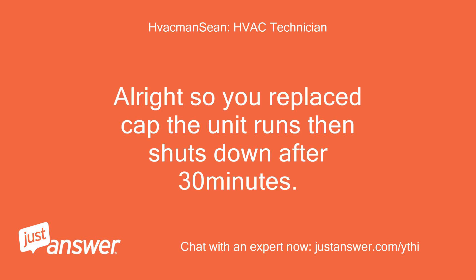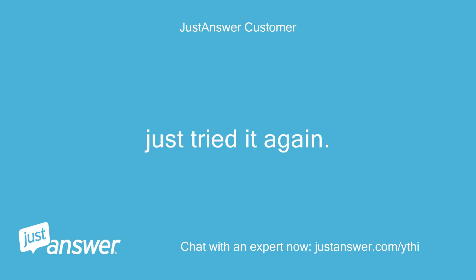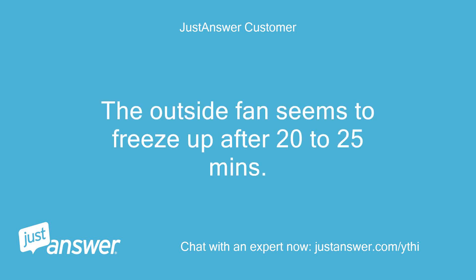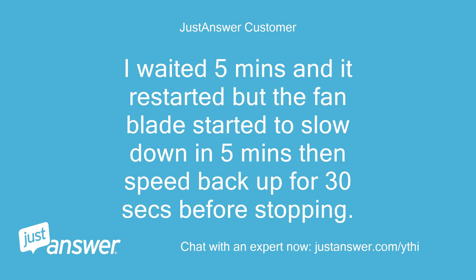Alright, so you replaced the cap, the unit runs then shuts down after 30 minutes. But does it restart without you cooling it down? Also, when it shuts down does the fan also shut down? Just tried it again. The outside fan seems to freeze up after 20 to 25 minutes. If I try to turn off and restart the system when it stops, the fan on the AC unit does not move. I waited 5 minutes and it restarted but the fan blade started to slow down in 5 minutes then speed back up for 30 seconds before stopping.